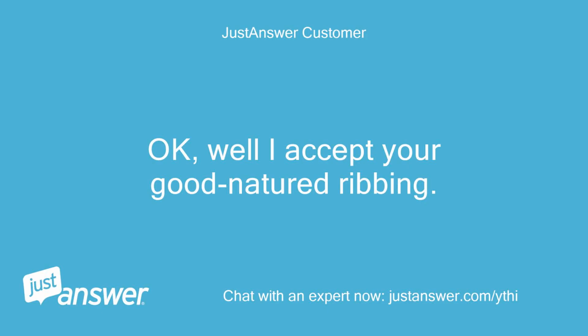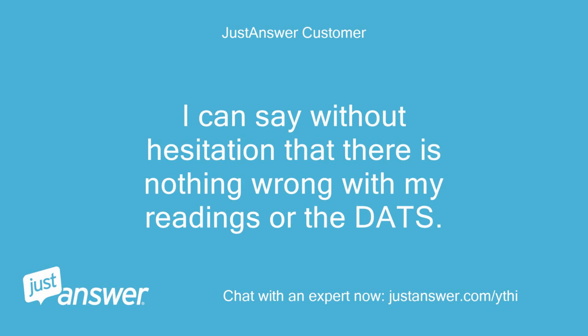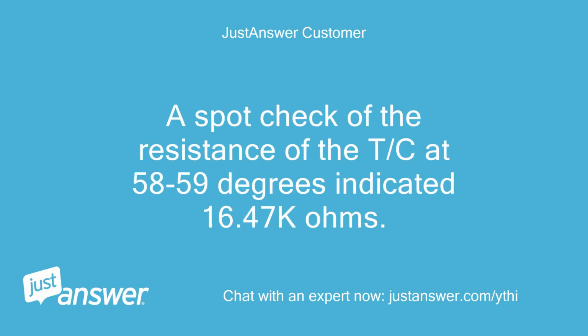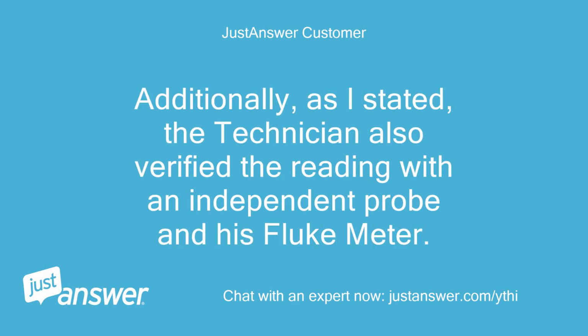Okay, well, I accept your good-natured ribbing. I wouldn't have lasted 39 years in the steel industry without a thick skin. I can say without hesitation that there is nothing wrong with my readings or the DATs. A spot check of the resistance of the TC at 58 to 59 degrees indicated 16.47 K ohms. The table shows 16.32 K at 58, or 15.89 K at 59. Additionally, as I stated, the technician also verified the reading with an independent probe and his Fluke meter.